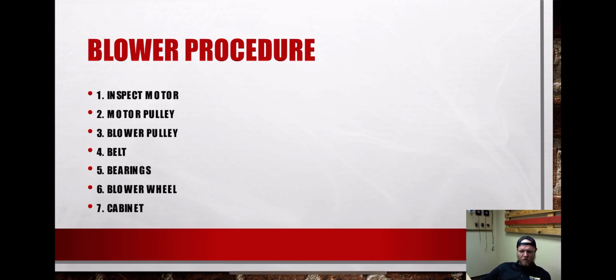Blower wheel. Inspect your blower wheel. Make sure that all the blades are still there. They're intact. Make sure they're not loose. Make sure they don't have too much buildup on them, because otherwise you're losing CFM. And then inspect your cabinet. Your cabinet should stay clean. If it's not clean, it's our responsibility to make sure that it does get clean. So figure out the way that you're going to clean it. Everything should look like we've given it some attention, and that is definitely something you guys need to remember. If you're doing a procedure and you're inspecting something, take a couple minutes and clean it. Everything's always going to work better if you clean it.